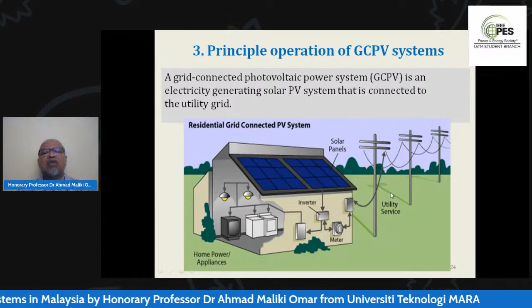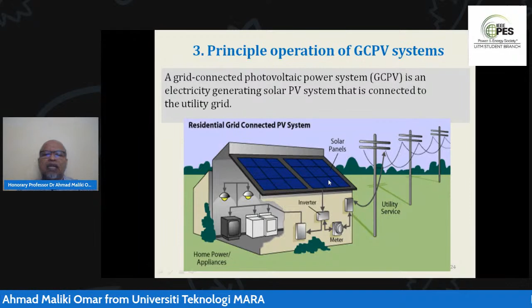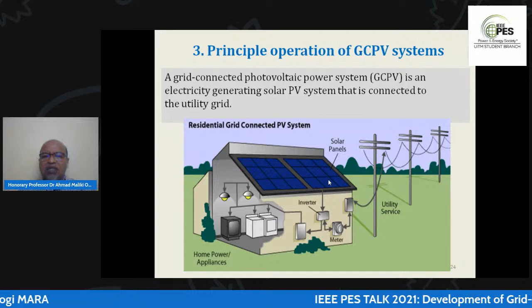If there is some interruption on the utility line here for whatever reason, maybe utility maintenance where they shut down the system, then the inverter must shut down automatically. The inverter must sense the presence of grid voltage here. Without grid voltage, the inverter will turn off. So we don't expect that if the grid is interrupted, you can still get power from the PV module here, unless you have another type of scheme which includes energy storage. But without energy storage, we do expect that the inverter also turns off.